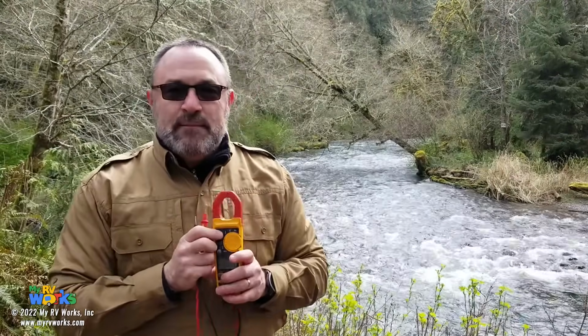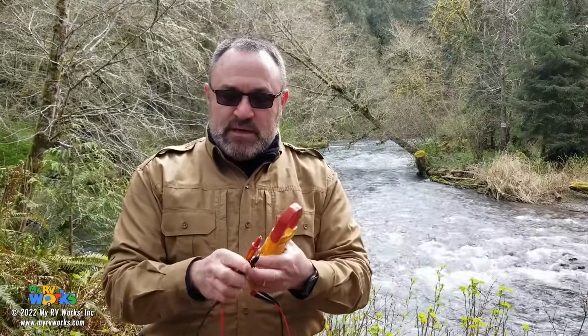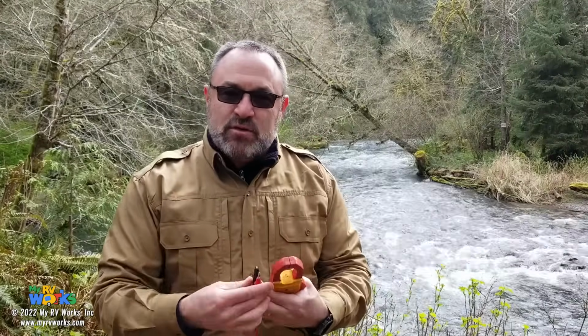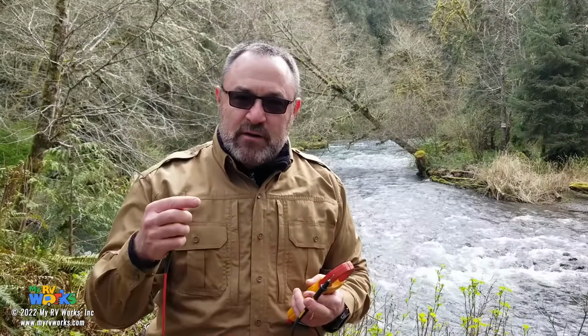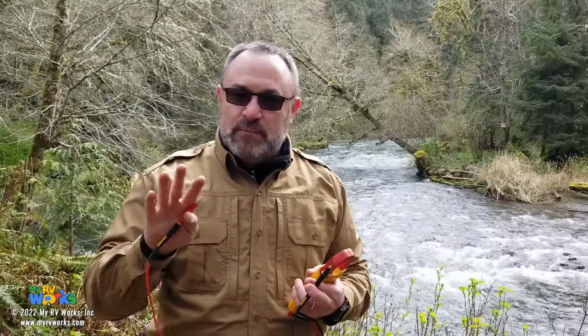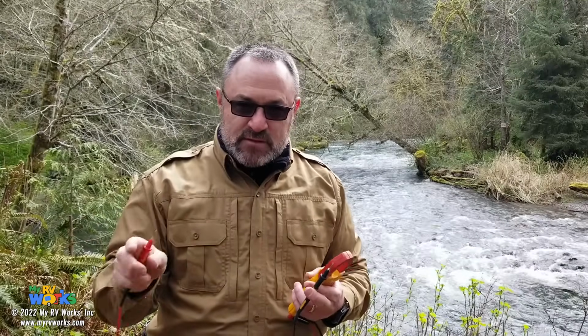When the meter is in that mode, take your red lead and touch it to the wire that you just took off that circuit breaker. Now all the power is off, you've unplugged it from everything, and the generator is off, so it's just a piece of wire right now, it's not energized.